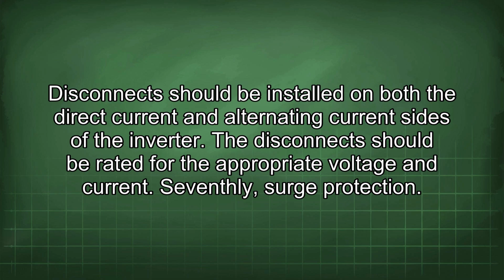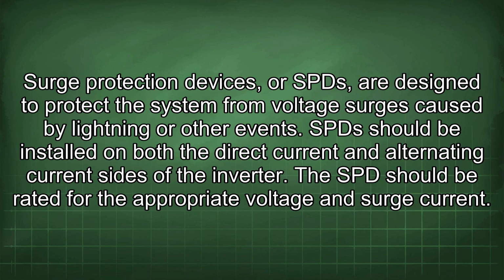Seventhly, surge protection. Surge protection devices, or SPDs, are designed to protect the system from voltage surges caused by lightning or other events. SPDs should be installed on both the direct current and alternating current sides of the inverter. The SPD should be rated for the appropriate voltage and surge current.